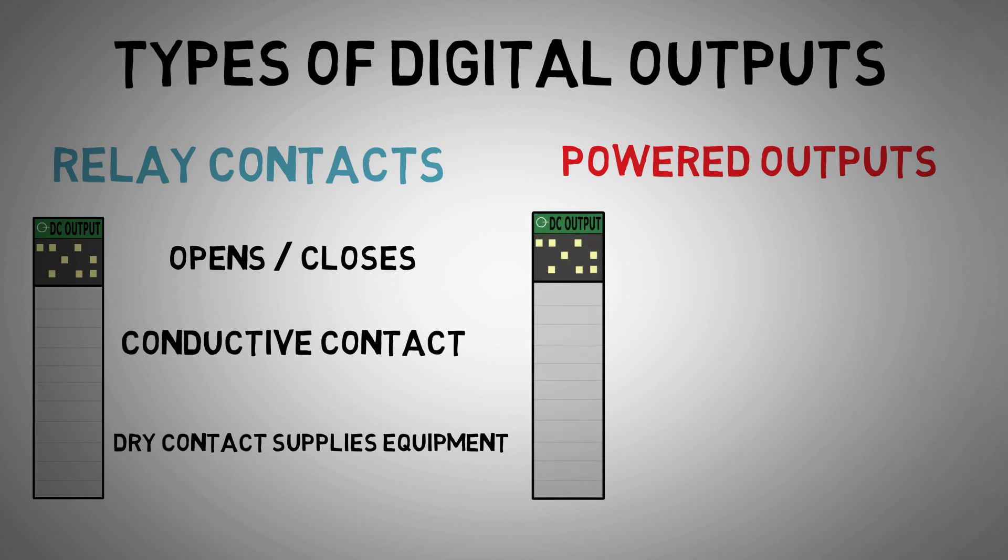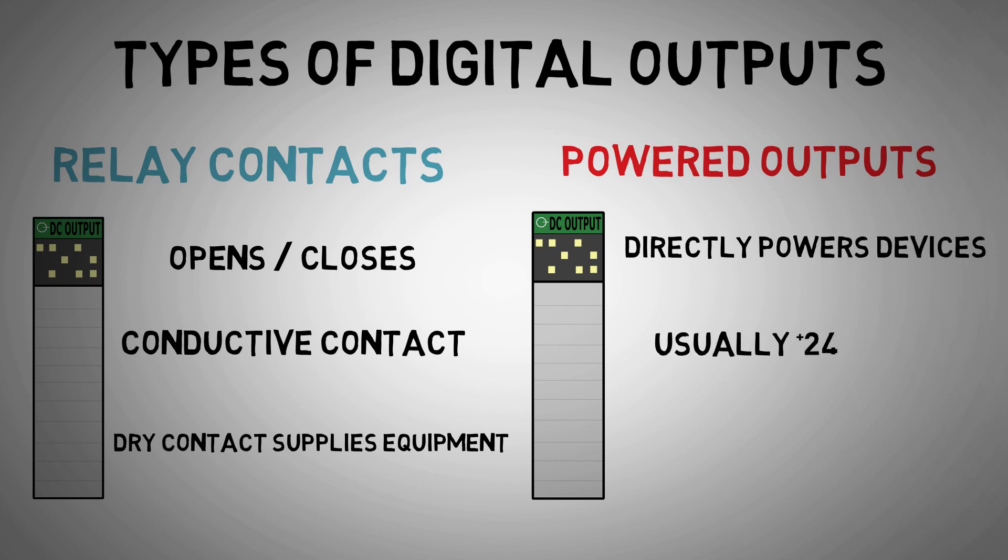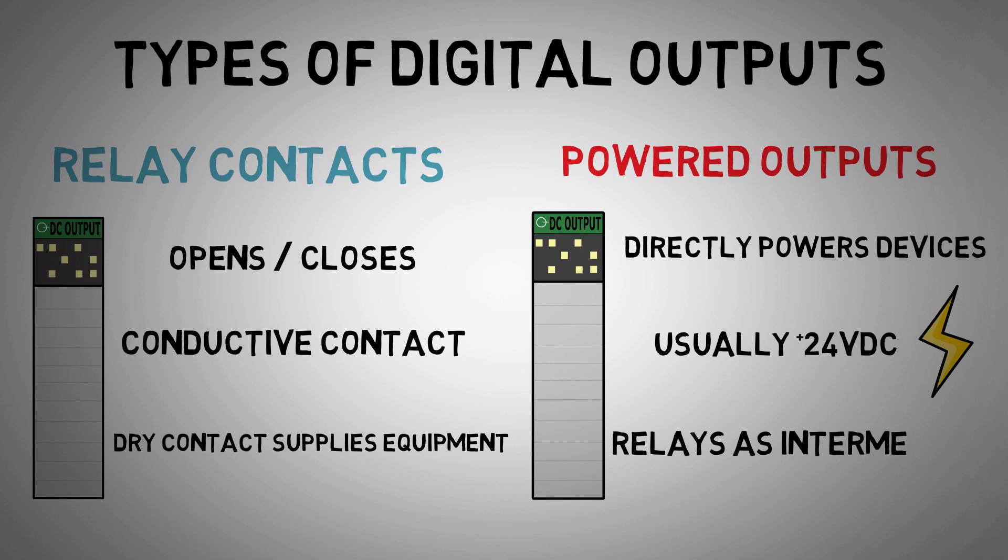Powered outputs provide voltage when the PLC processor signals the output to turn on. Usually 24 volts is supplied from the output. In this format, equipment might be powered directly from the output card, but separate relays are often used as intermediaries.